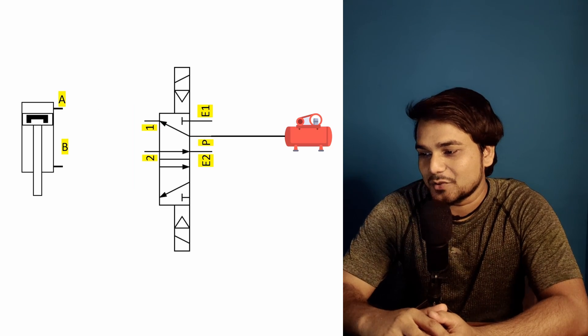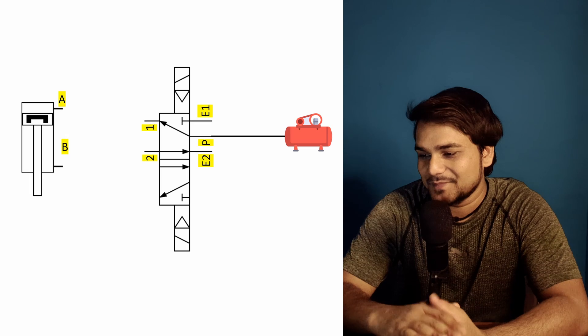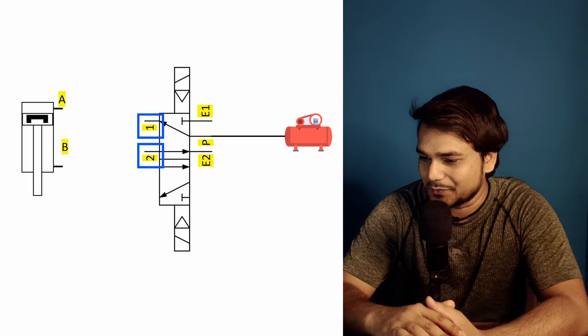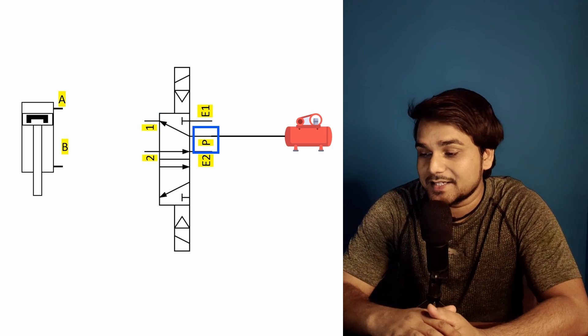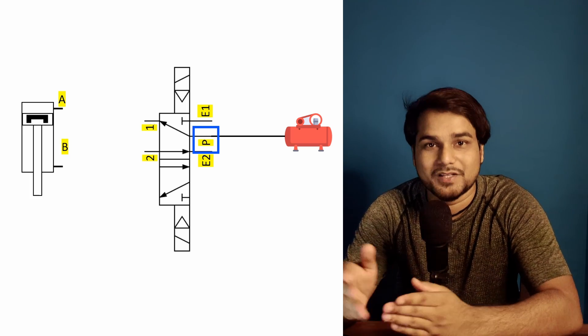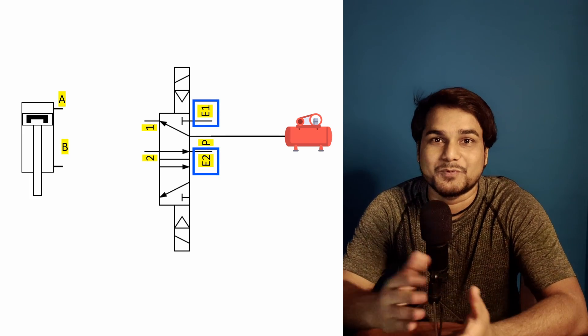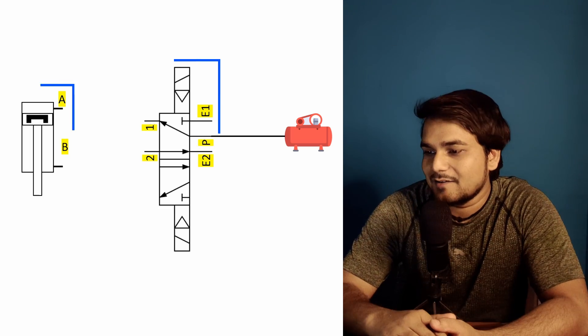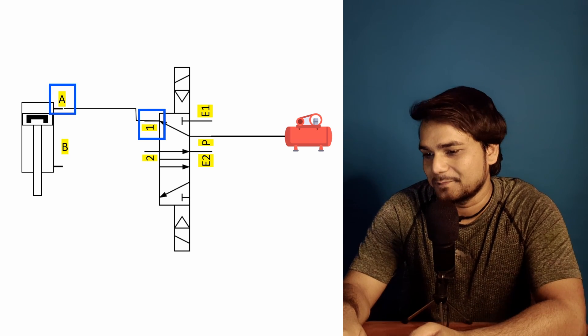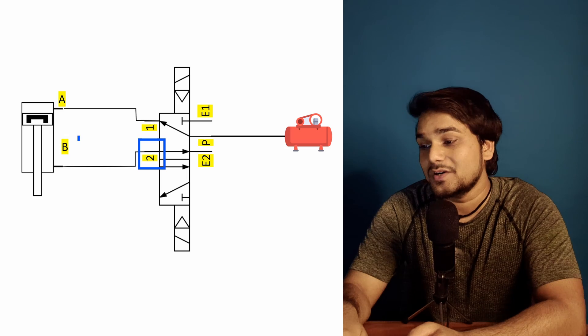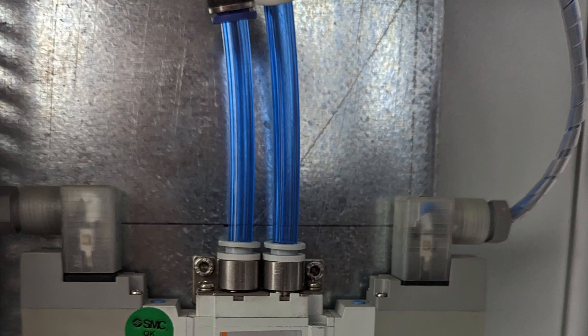I am placing a 5/2 directional control valve here. There are two ports on the left side — port 1 and port 2 — which connect to the pneumatic cylinder ports. On the right side there are three ports: the middle port is the compressed air supply port, indicated as P for pressure, and the other two are exhaust ports E1 and E2. Now I am connecting valve port 1 to cylinder port A and valve port 2 to cylinder port B using a soft nylon pneumatic tube.